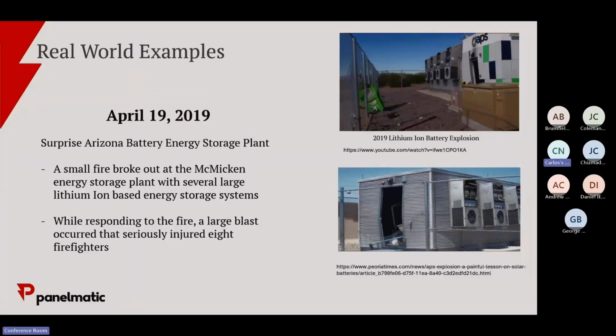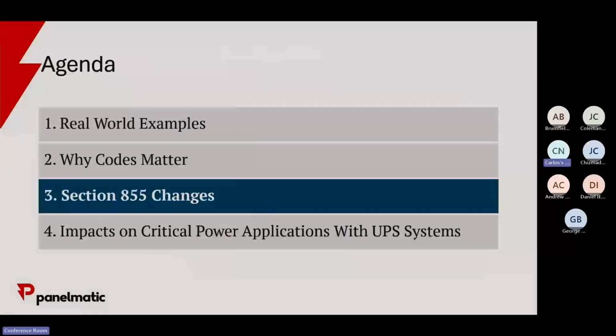You mentioned at 40 kilowatts they were talking about in-rack battery systems. The code doesn't specify exactly what it is, at least from an NEC standpoint, though IBC puts it at 70 kilowatts for lithium-ion. Do we have anything that small? That's the problem—no. We're talking megawatts; in-rack and in-row systems are small.